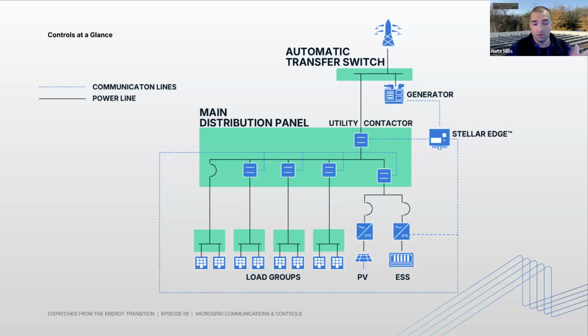During that time, you could be in grid forming or grid following, depending on the OEM. Again, we'll charge the battery up, turn the generator off. The utility contactor will see that as a loss of power and open just like normal, and the battery will be back in grid forming. And we do that dance continuously until the power comes back. So that's how this system will work.